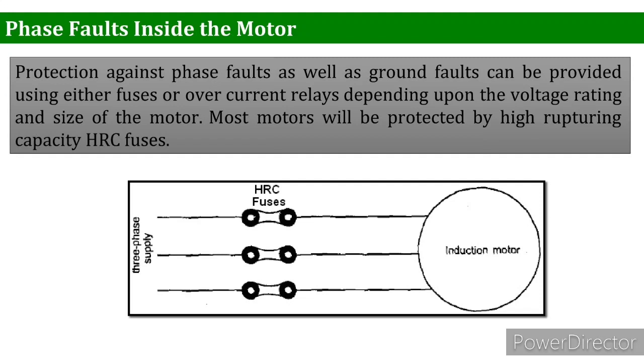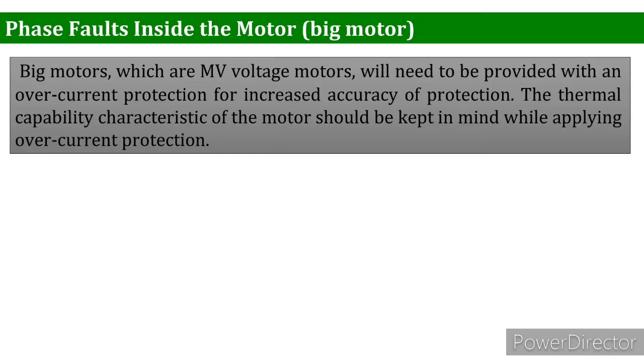As you can see from the figure, there is an induction motor and three HRC fuses, one installed on each phase. So in the case of a big motor, what will happen? Big motors, in the medium voltage, or MV, range, will need to be provided with overcurrent protection for increased accuracy of protection. The thermal capability characteristic of the motor should be kept in mind by having the data sheet of that motor while applying the overcurrent protection.